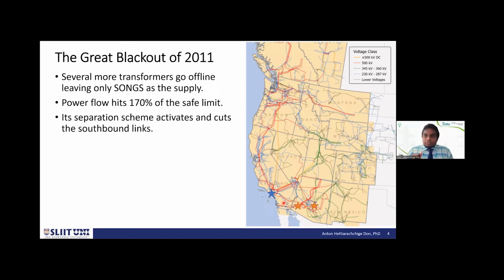So 170% is reached. There is a little bit of time before safety actions start taking place, but nothing is done. Then the automatic systems take control and shut down the power flowing south of there, into the San Diego area. It's a safety mechanism to safeguard the transformers and generators at this switchyard.